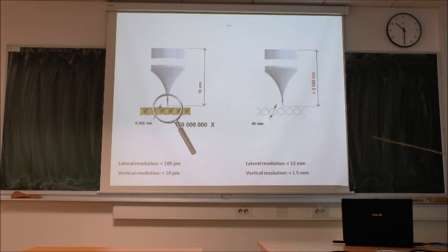You can do this nicely with piezo crystals. But how to stabilize the whole system, the whole instrument, so that this distance will be constant. So we don't have the mechanical noise, this doesn't vibrate, this doesn't move. And this is basically what defines a good instrument. So how stable your tunneling conditions are. Next thing, scanning tunneling spectroscopy.